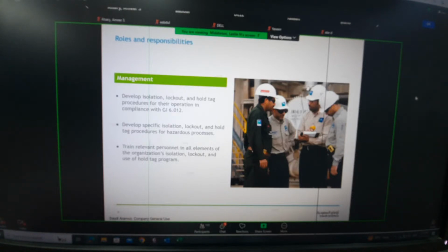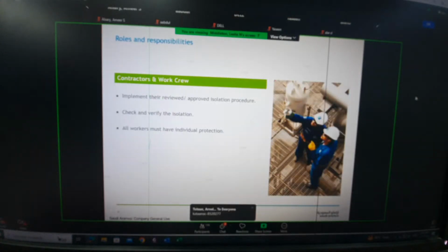Personnel must be thoroughly trained, as per Saudi Aramco requirements and the relevant GIs, to participate in the programme and properly implement all elements of it, including the location of isolation points and the devices used to achieve proper isolation. Contractors and work crew must check and verify isolations before work begins and ensure implementation is in line with their reviewed isolation plan. Individual protection: each individual worker, including contractors working on equipment, must install their personal locks and tags at isolation locations.